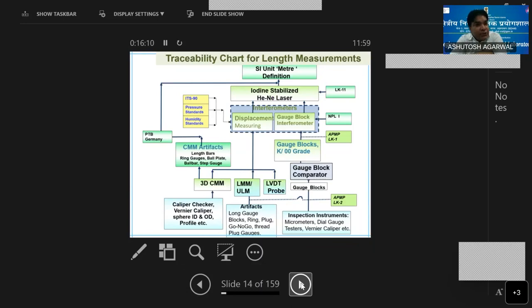We realize the SI unit meter using an iodine stabilized helium neon laser. For this laser, we did the intercomparison LK1 that I told you about. Then we have two interferometers, displacement measuring interferometer and laser interferometer. We generally do LMM calibration, CMM calibration and other things. Then there is the gauge block interferometer, for gauges and other things. Using the gauge block interferometer, we calibrate your K grade and zero grade. From this we calibrate our gauge block comparator, and from the gauge block comparator, we calibrate the gauge blocks.